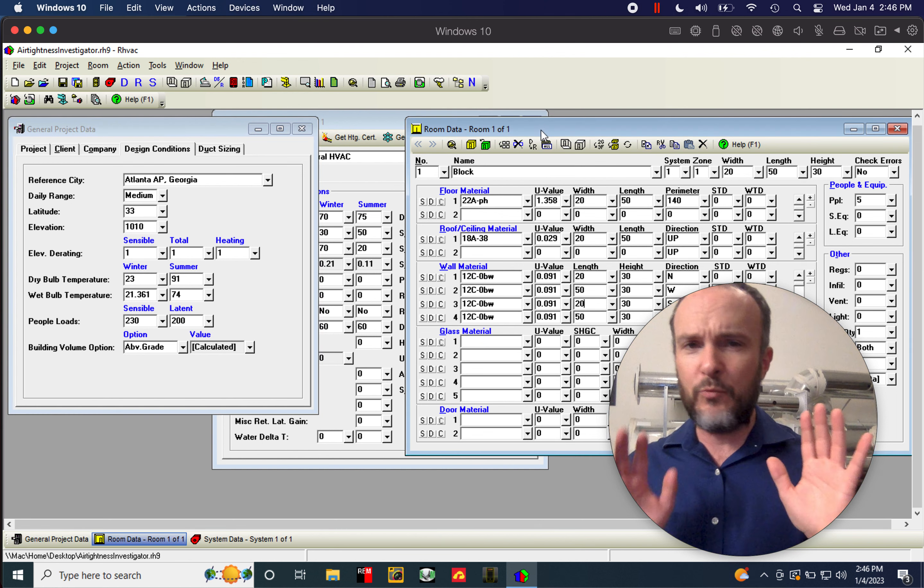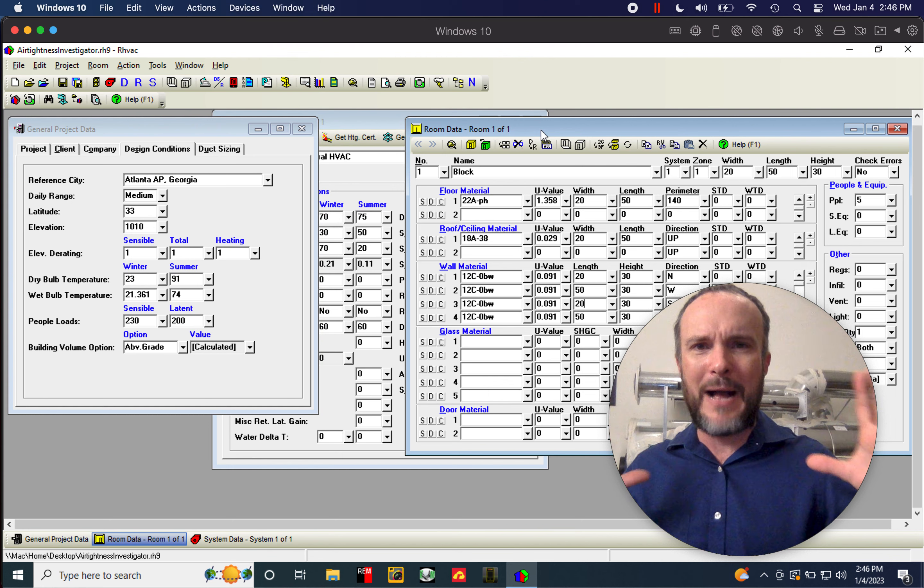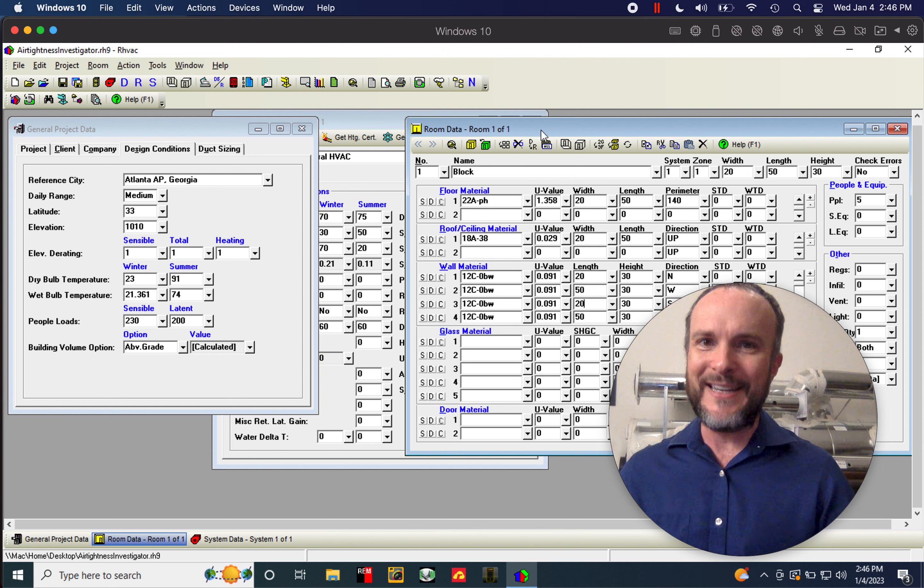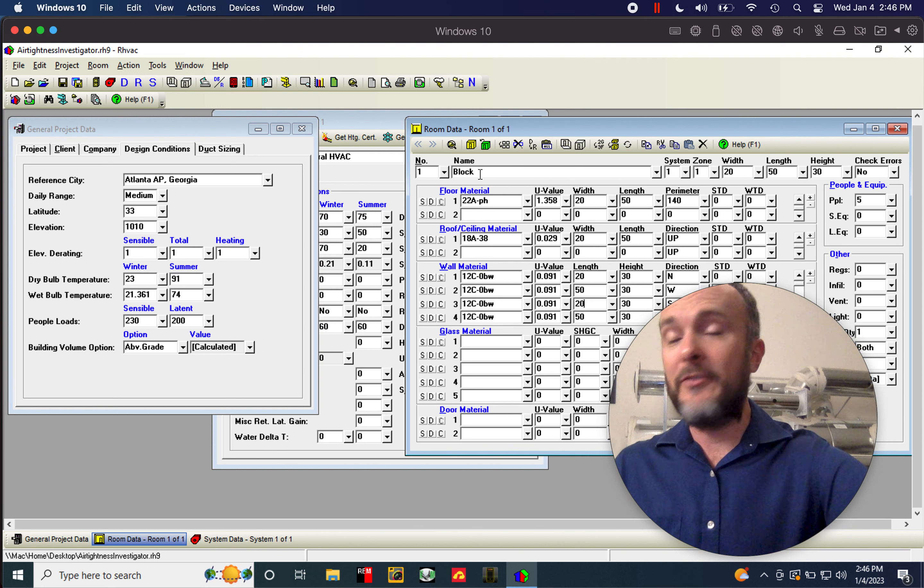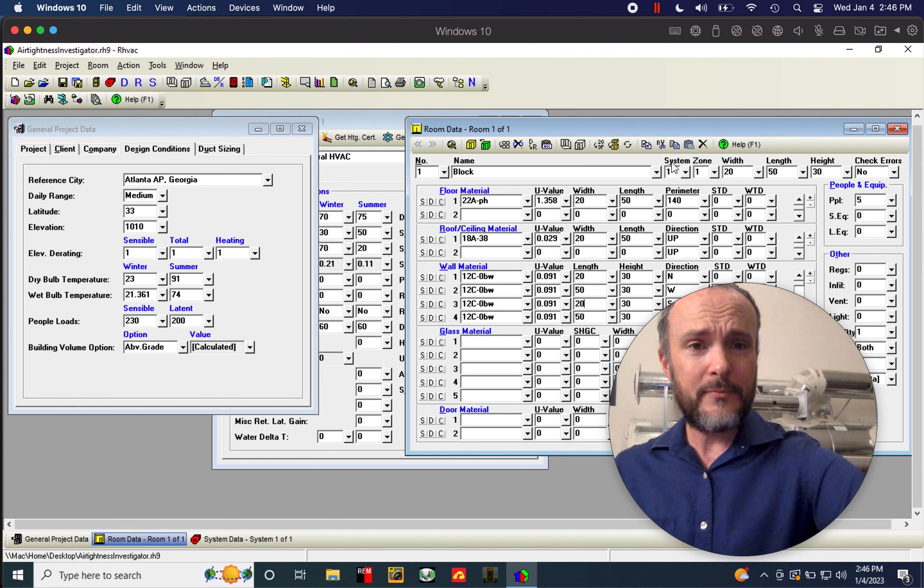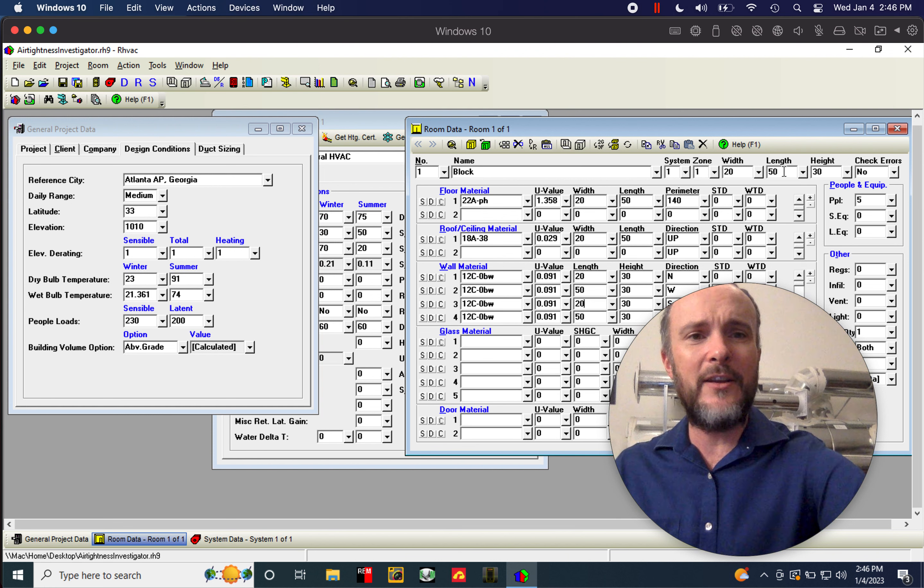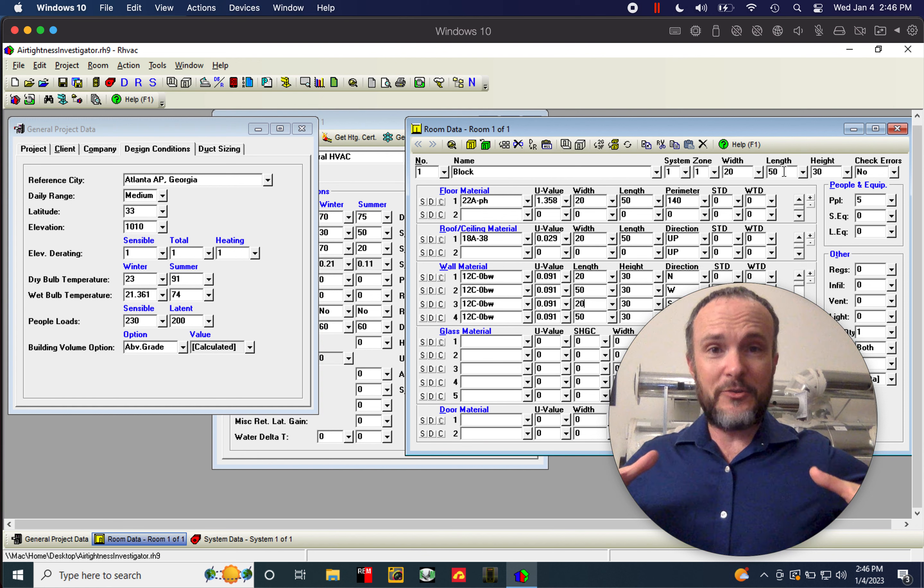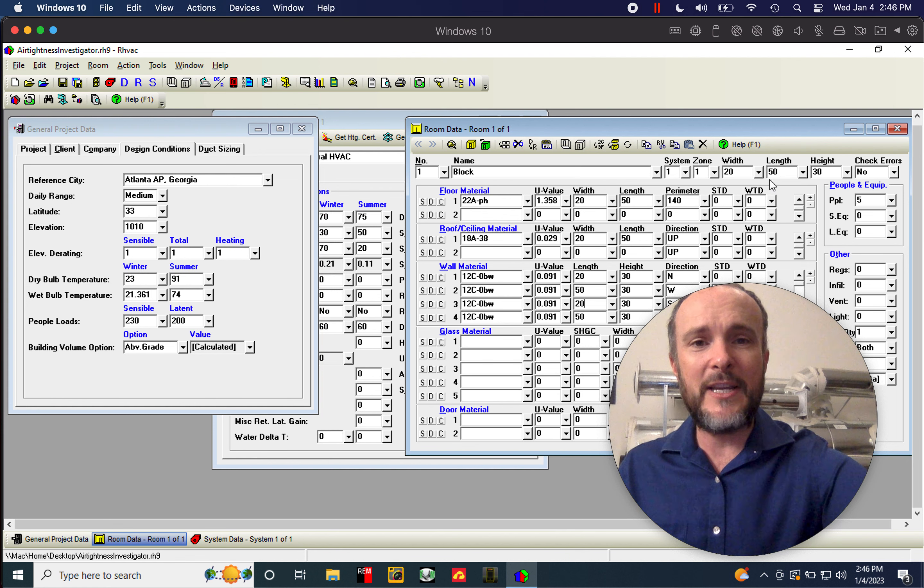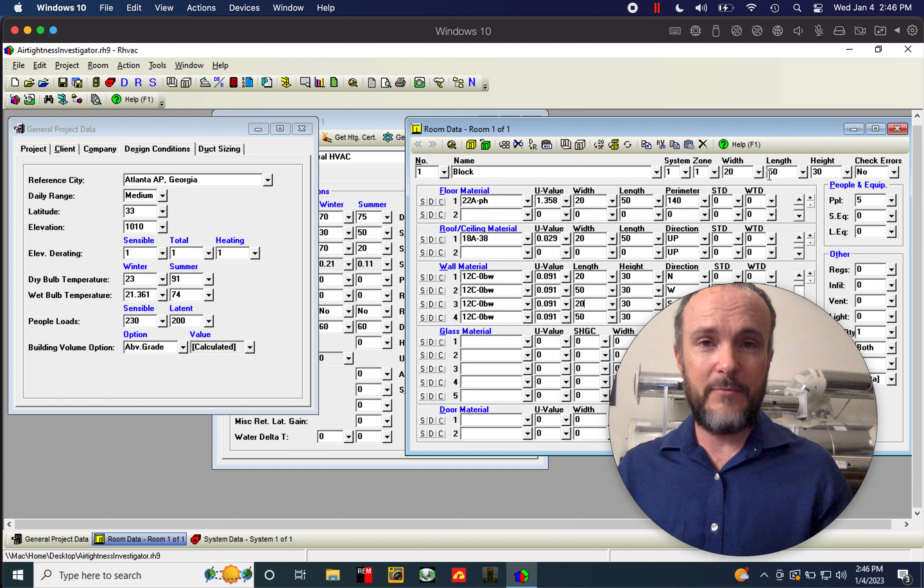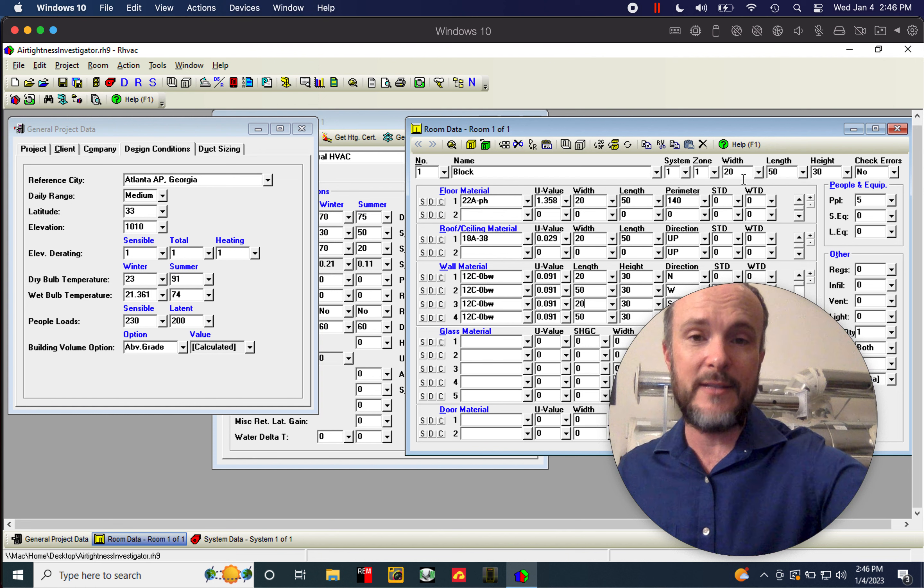I have a block load, which is the really cheesy way of doing this. It just treats the whole house as one big box. I don't recommend doing that if you actually want to know how many BTUs need to go into each room, how much heat bleed there is through each and every room. But for this case, all we need to do is the volume. So you can see I've got a 20-foot wide, 50-foot long box that is 1,000 square feet. And I've got three floors in that, so a 30-foot height that gives us a volume of 30,000 cubic feet, which is a pretty standard volume for homes today.